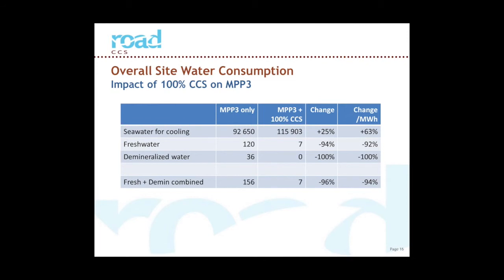For freshwater usage, you can see that we have almost eliminated this entirely. So the only freshwater usage is our nominal amount to cover the wastewater that's coming out from the demin plant. So in this configuration, we've almost got a water neutral power station apart from the cooling, and because we've got direct seawater cooling, that's not a big problem. So that's the end of the sort of main technical part of the presentation. The conclusions just give a recap.